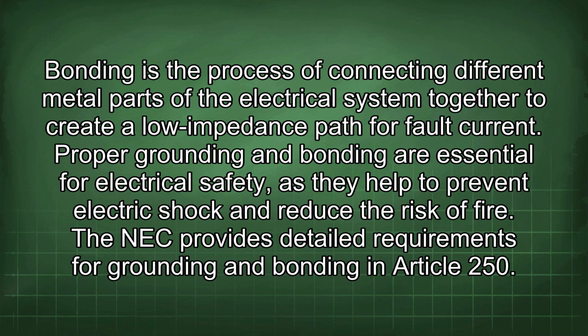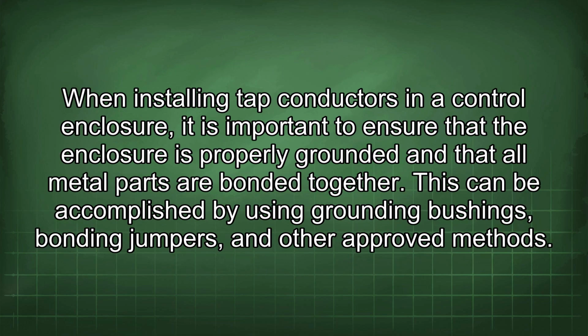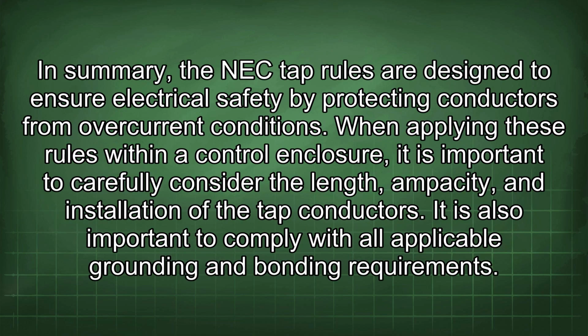The NEC provides detailed requirements for grounding and bonding in Article 250. When installing tap conductors in a control enclosure, it is important to ensure that the enclosure is properly grounded and that all metal parts are bonded together. This can be accomplished by using grounding bushings, bonding jumpers, and other approved methods. In summary, the NEC tap rules are designed to ensure electrical safety by protecting conductors from overcurrent conditions. When applying these rules within a control enclosure, it is important to carefully consider the length, ampacity, and installation of the tap conductors. It is also important to comply with all applicable grounding and bonding requirements.